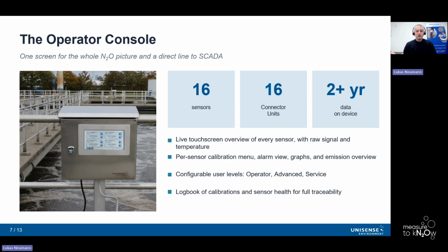Then we have the console, the part that you see day to day. The numbers are 16 sensors per console, 16 connector units, if you want to set it up that way. We have 2 years of measurement data stored locally, and 1 year of calibration logbook saved locally as well. It's a live touchscreen overview of every sensor, the respective concentrations, temperature, and raw signals, all available at a glance. You have the per-sensor menus. So for every sensor connected to a console, you can check the calibration, alarms, graphs, and the overall emissions overview.